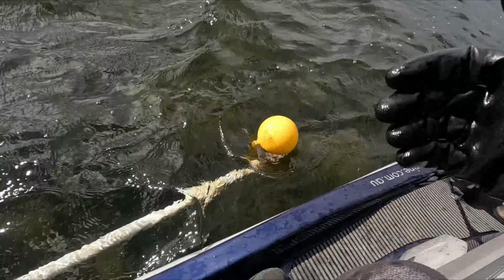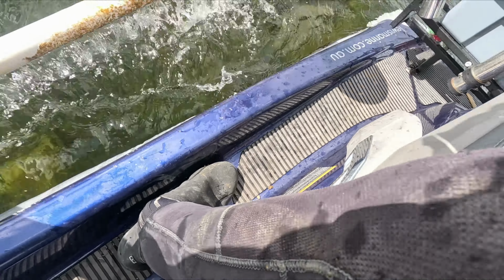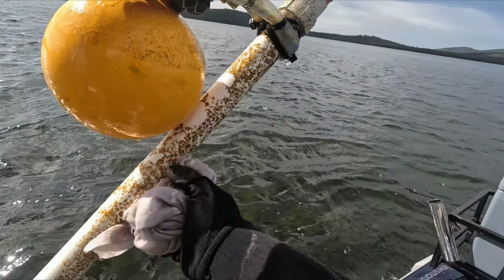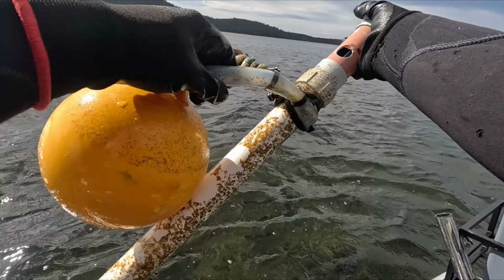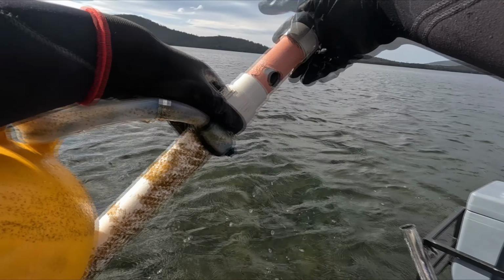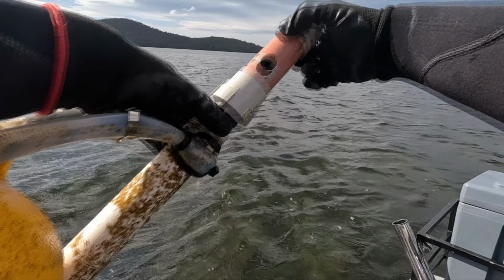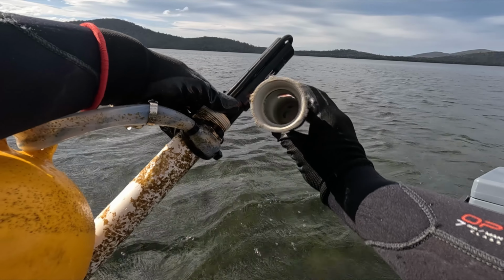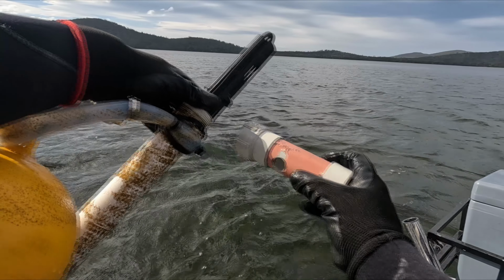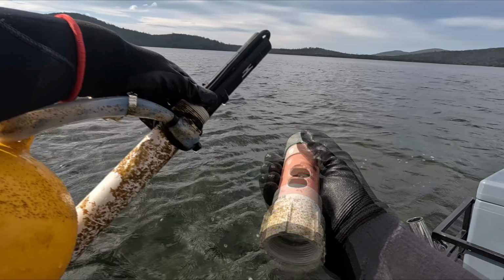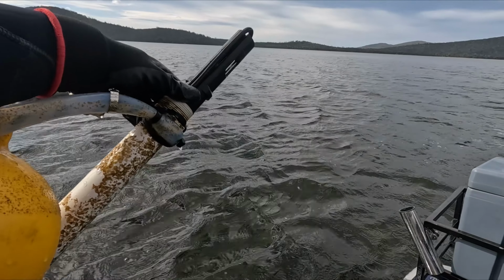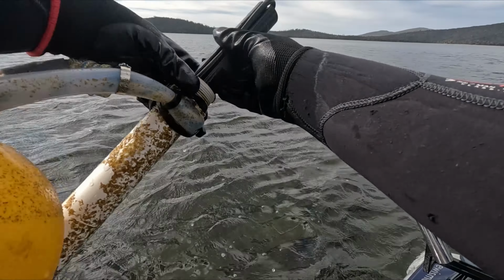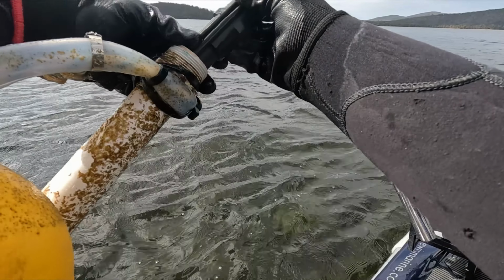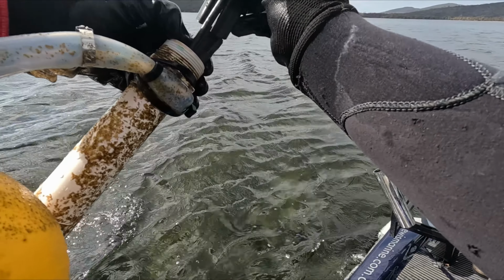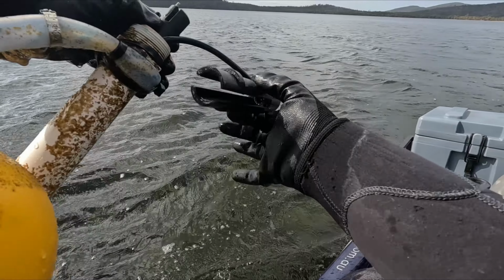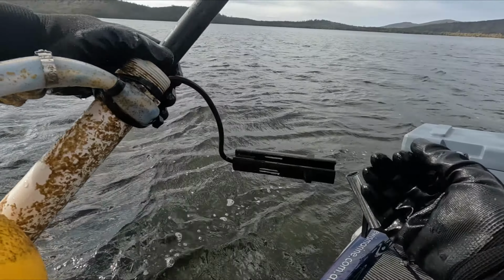When it comes to calibration, we start off with the same process as a clean. Pull it out, give it all a scrub. But for calibration, we really want to get in here and take a good look inside. Make sure nice and clean inside the sensor cap. If this is damaged or really dirty, then we can replace it with a new one. But that one looks pretty good. In here, we have the sensor and the protection for the sensor. So this is for the protection, and this itself is the sensor.